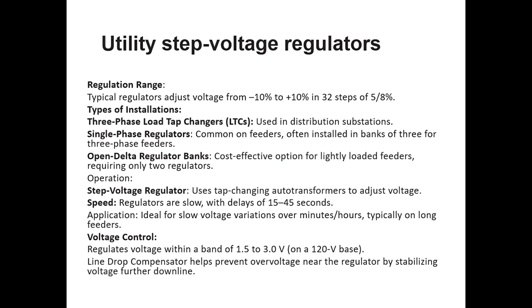Now the next slide is about utility step voltage regulators. Regulation range: typically regulators adjust the voltage from -10 to +10% in 32 steps of 5/8% or 5 to 8%. Type of installation: three-phase load tap changers are used in distribution substations, and single-phase regulators are common on feeders, often installed in banks of 3 on 3-phase feeders. Then we can use the open delta regulator bank, a cost-effective option for lightly loaded feeders requiring only 2 regulators. Operation: the step voltage regulator uses tap changing auto transformers to adjust the voltage. Speed: the regulators are slow, with a delay of 15 to 45 seconds. Application: ideal for slow voltage variations over minutes or hours, typically on long feeders.